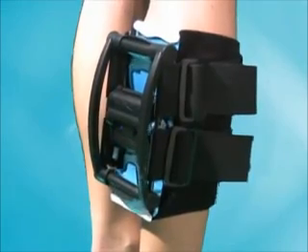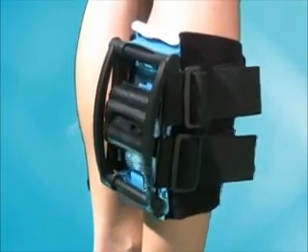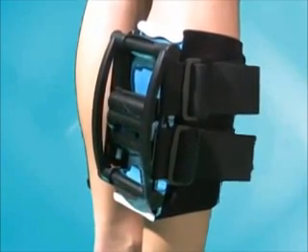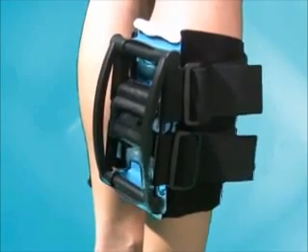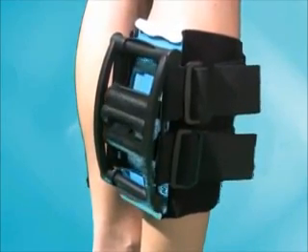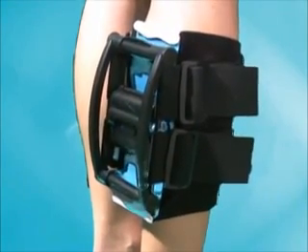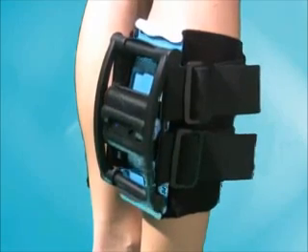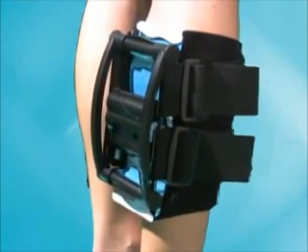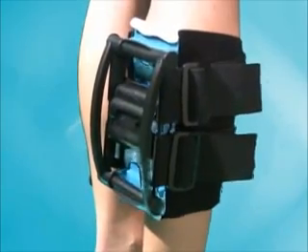In fact, after two minutes, popliteal blood flow is increased by 64%, and after 50 minutes, femoral blood flow is increased by 88%. As you can see, each wave begins at the distal end of the calf and volumetrically displaces blood flow as it moves up the calf muscle. The VenaWave displaces up to one liter of blood every minute, a rate conducive for preventing deep vein thrombosis.